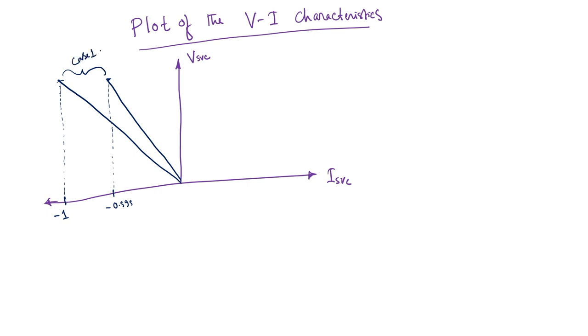So this is the sub-range of case 1. Any value of VAR production is possible in between this range by controlling the TCR unit. In fact, the controllable parameter here is the TCR unit only. By controlling the TCR parameter, we can vary this.